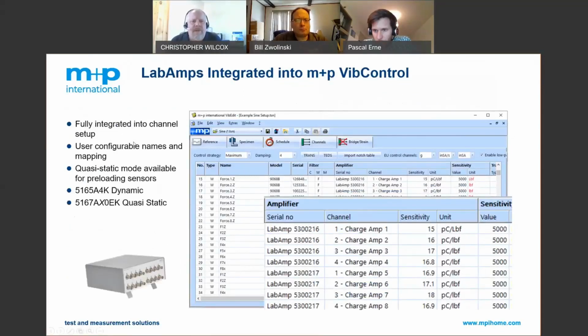The reason that M+P chose the lab amps for this application was that the quasi-static mode of the 5167 allows it to be preloaded out to very high force levels. Additionally, it has the long time constant that you need to use when performing a preload. The software is now integrated, the interface is now integrated, and I'll show you that quickly in a little bit. Basically, all of this information is then also stored in your result file for future traceability.